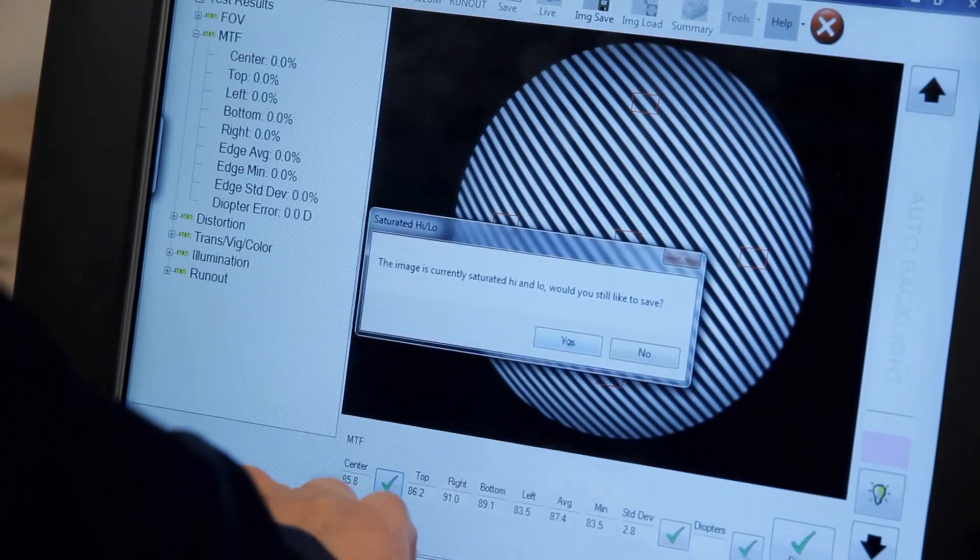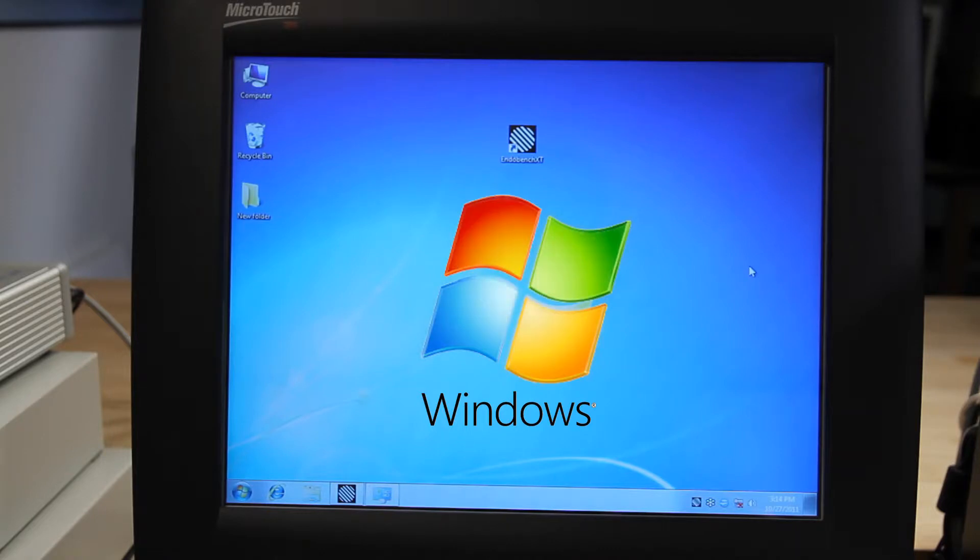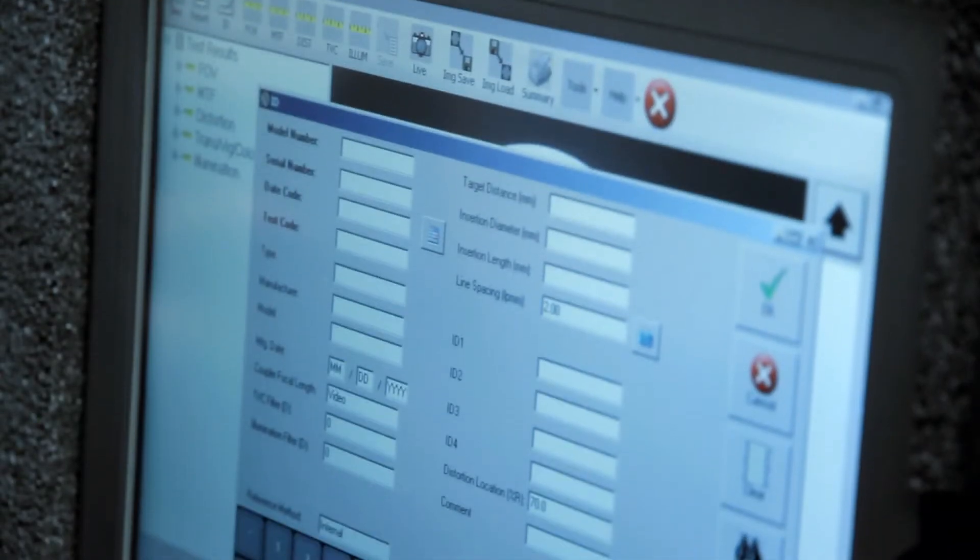Once the measurements are completed with the EndoBench, it's important to present the results in an easy-to-understand format. By utilizing the Microsoft Windows platform, the EndoBench has the ability to export data to an Excel spreadsheet, an Access database, or as a PDF.